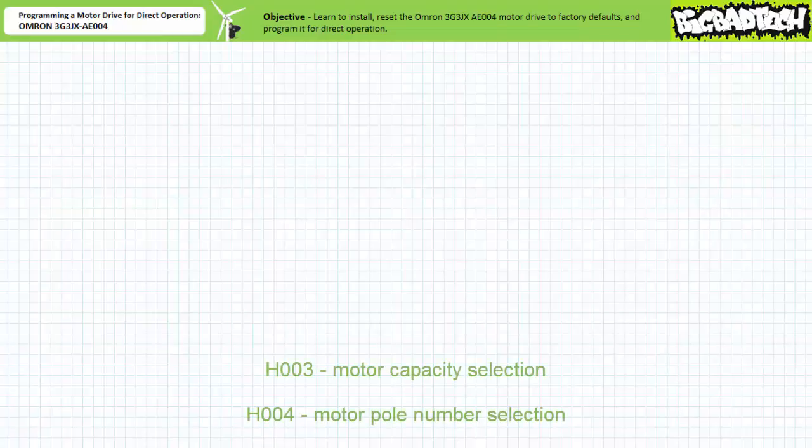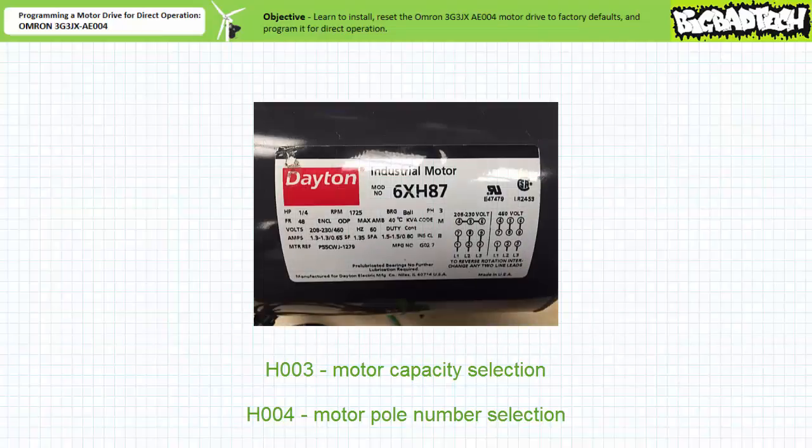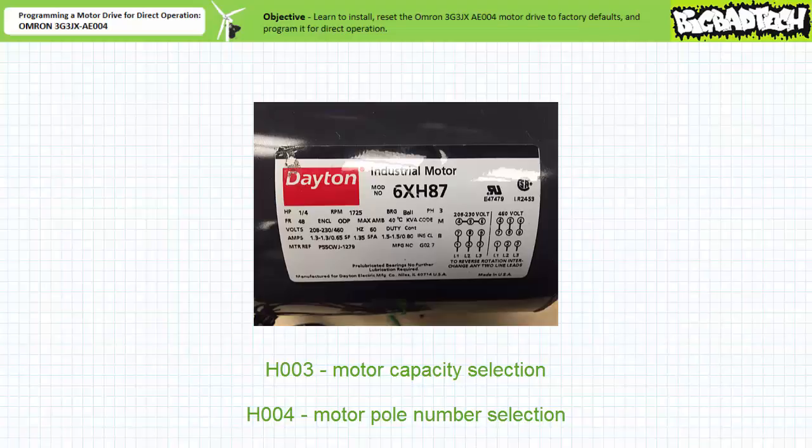Now we need to program this drive to recognize what type of motor we'll be driving. One does so by entering the motor nameplate into the motor drive using the motor parameters preceded by an H, notably H003 motor capacity selection and H004 motor pole number selection.